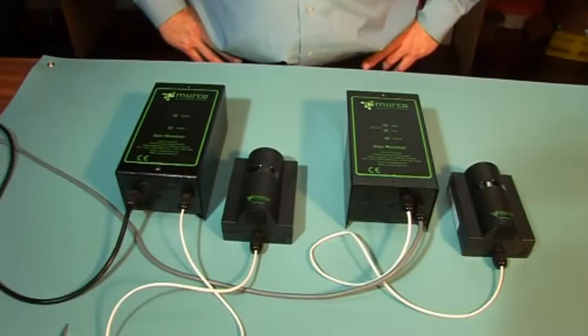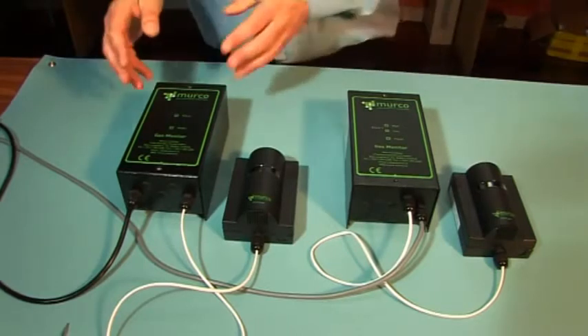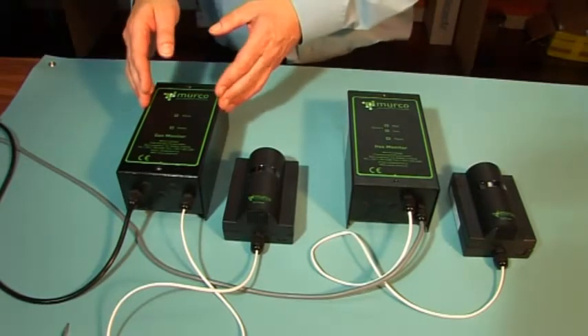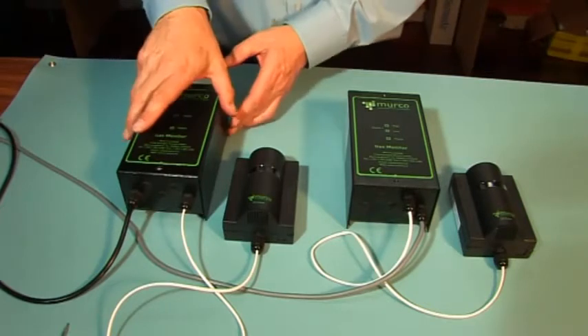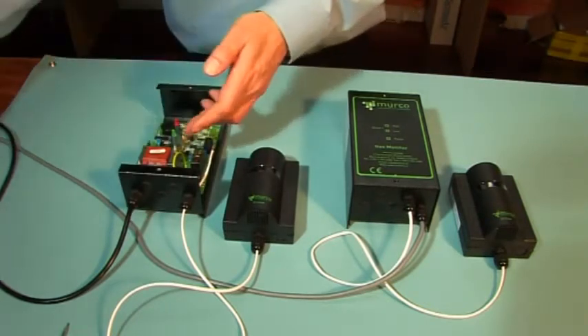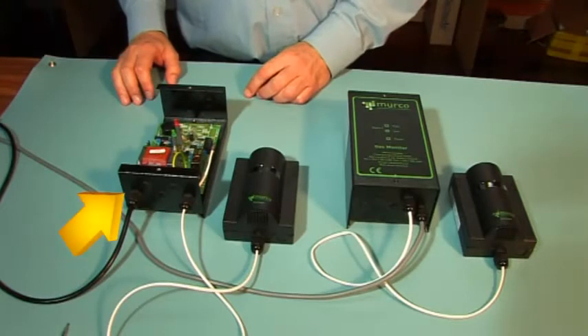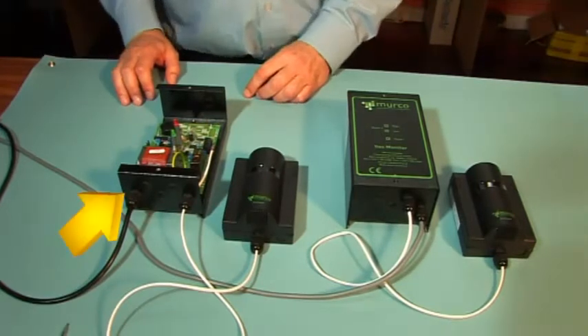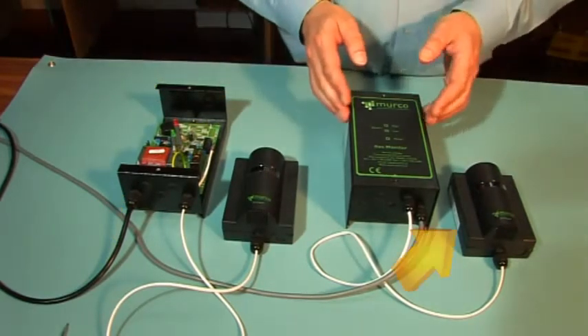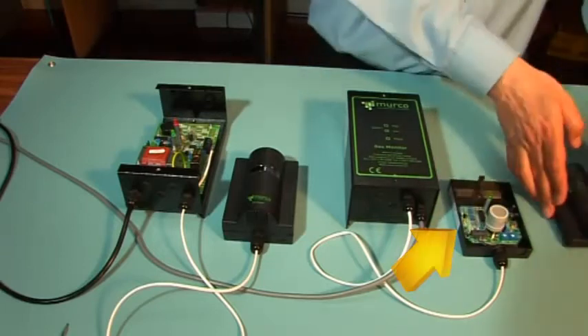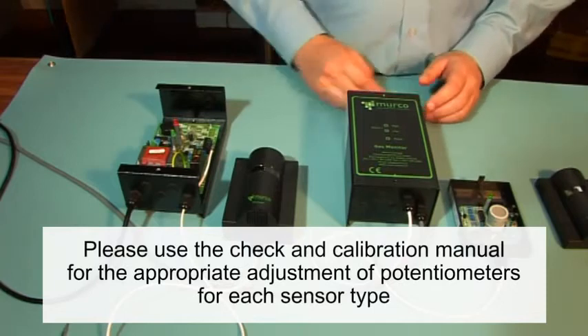The MGD has models for 1 or 2 levels of alarm and can range from 1 to 6 sensors connected to the controller. On the 1-level systems, the calibrations are carried out on the controller, and on the 2-level systems the calibration is carried out on the sensor. For demonstration purposes, we shall use a 1-channel unit for both the 1 and 2-level systems.